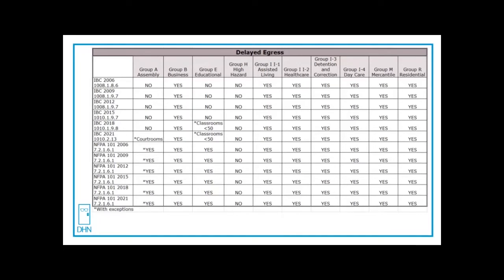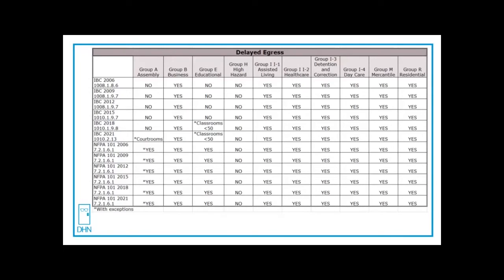Group A assembly is not permitted in IBC until the 2021 edition, and then it's just courtrooms. In NFPA 101, there are some exceptions where they do allow it in assembly occupancies. Group B business and Group M mercantile are the most common places where you will see delayed egress.